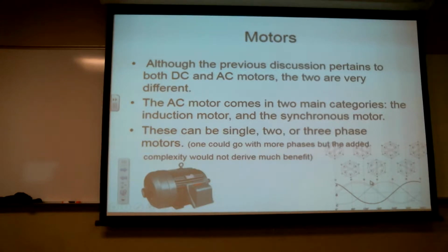So there are 7 three-phase motors in this building. Now you'd think it's a 50-50 shot that each one would be hooked up either the right direction or the wrong direction, right? All 7 of them spun the wrong direction in this building. When they did the remodel and everything got hooked back up, they all went the wrong direction.